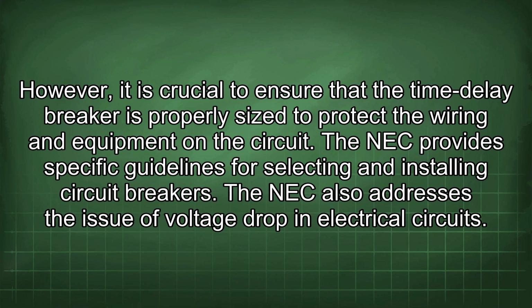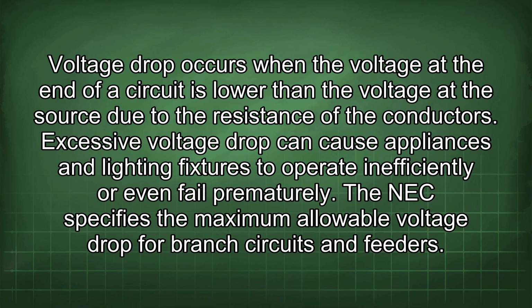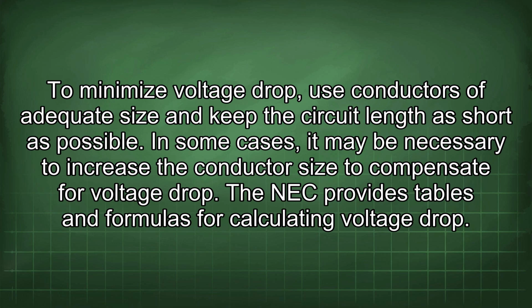The NEC also addresses the issue of voltage drop in electrical circuits. Voltage drop occurs when the voltage at the end of a circuit is lower than the voltage at the source due to the resistance of the conductors. Excessive voltage drop can cause appliances and lighting fixtures to operate inefficiently or even fail prematurely. The NEC specifies the maximum allowable voltage drop for branch circuits and feeders. To minimize voltage drop, use conductors of adequate size and keep the circuit length as short as possible. In some cases, it may be necessary to increase the conductor size to compensate for voltage drop. The NEC provides tables and formulas for calculating voltage drop.